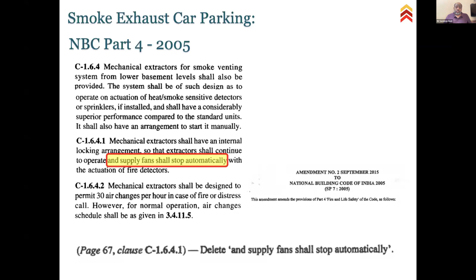The fan has to be stopped automatically when the fire has occurred, but once the fire is finished, you have to start those fans to dilute the smoke out of the space. So we addressed this in the amendment to the National Building Code of India and removed this word, because the concept was not clear to people. That's why we now talk about makeup air requirements—where the makeup air should be, and the provision of makeup air to the exhaust system.